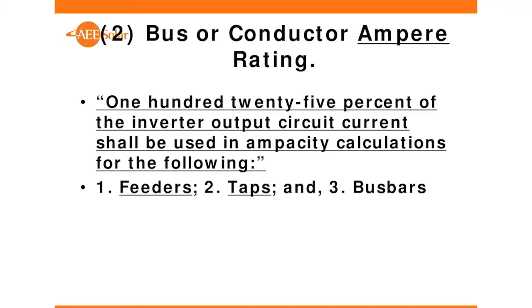So what this says is that for all our calculations, we're going to use 125% of the inverter output circuit current. So now the microinverter, which has a 1 amp output, is really considered a 1.25 amp output for the purposes of doing our calculations, and we run our calculations all based on that for our maximum number of this and that and the other thing.